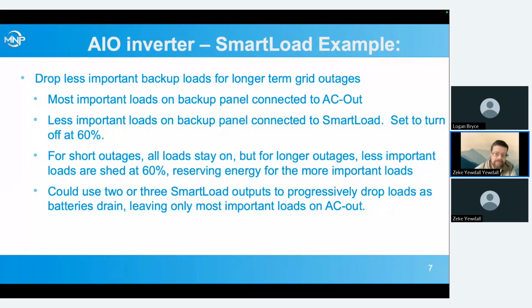One thing, probably the first thing that comes to mind, is dropping less important loads if our batteries are getting low. If we're grid tied and we've got a longer term outage, maybe we segregate our backed up loads into 2 backup panels, one on the AC out and one on one of our smart loads. The less important ones on the smart load, we can set to turn off at, say, 60%. You can pick whichever value you think is appropriate. As our batteries are discharging, to begin with, we're running all the loads. But if we hit 60%, we're thinking, well, we want to save that energy for our more important stuff and not waste it on big things that we don't really need. So for short outages, all the loads stay on, but if we've got a longer outage and the batteries start draining, we can dump a bunch of those loads on the smart load, reserving the energy.